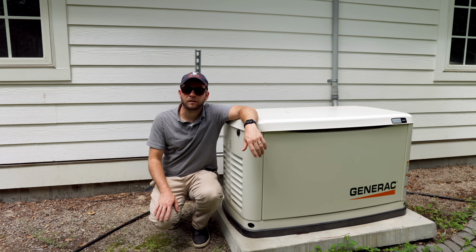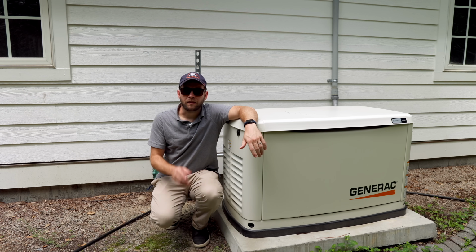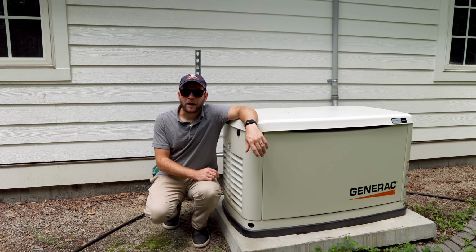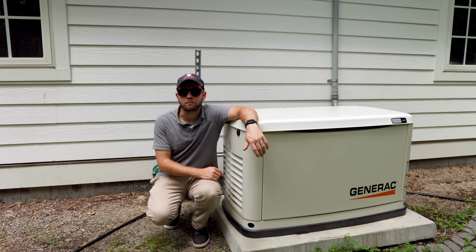This is a 16 kW Generac Guardian. This model is actually discontinued, being replaced with a smaller one and a larger one. But pretty much all of them are about the same. This is an air-cooled generator, so it does not have coolant lines and radiators and things like a car engine does. It's more like an old Volkswagen Beetle in that sense. But essentially, this has a large enough engine that it can maintain a significant amount of power. 16 kW is actually on the smaller side for backup generators.